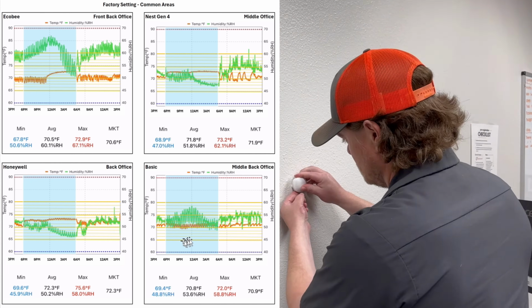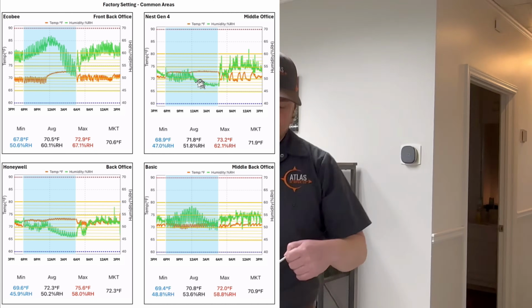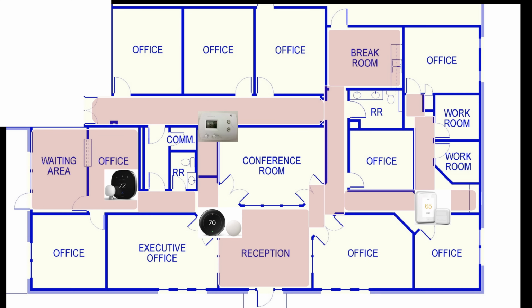At 6 a.m., somebody had to manually turn it back on. Our basic thermostat ran all night wide open, largely because these 3 units are off. The red areas are the common areas in our office, and all 4 systems feed this area, so the temperatures here rise and lower together. With 3 systems off and only 1 running, it runs constantly trying to satisfy the temperature for the entire area.